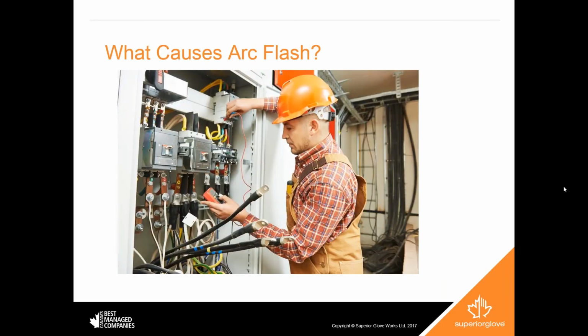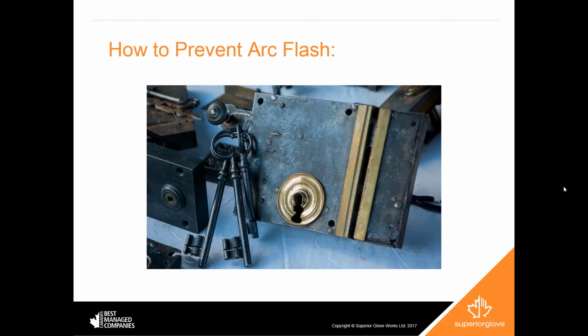So always keep in mind what the voltage is on the piece of equipment that you're working on. Matt? Yeah. So what causes an arc flash? Unfortunately, most arc flashes are caused by human error. Our presenter, Matt Tonkin, gave the statistic at the beginning: 2 out of 3 electrical injuries are a result of worker error. So it's things like working on energized equipment, not properly using lockout and tag out devices, and a lack of upkeep to machinery. It can also happen when you're working on de-energized equipment but leave a wrench or a tool in the area. Once that machine is re-energized, those types of things can cause arc flashes to occur. So I'll pass this back to you, Robert.